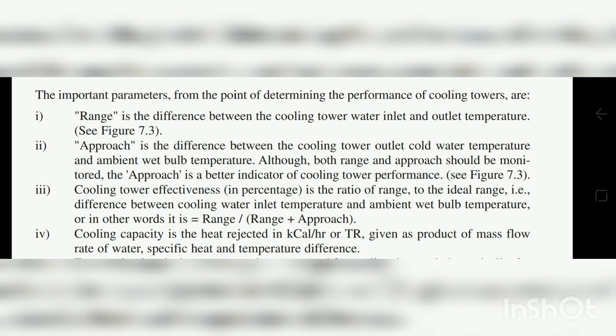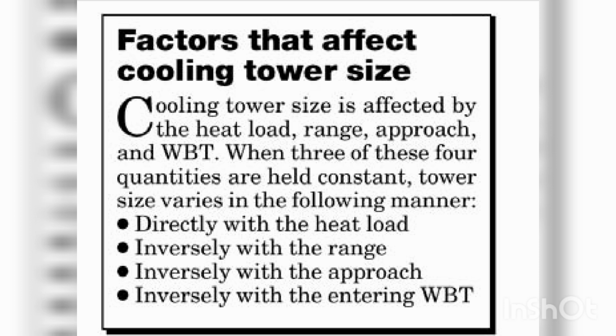The factors that affect cooling tower size include heat load, range, approach, and entering wet bulb temperature. Cooling tower size varies directly with heat load and inversely with range, approach, and entering wet bulb temperature. So if range increases, the required cooling tower size decreases; similarly, as approach or wet bulb temperature increases, the size decreases.